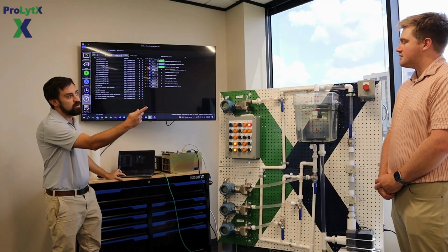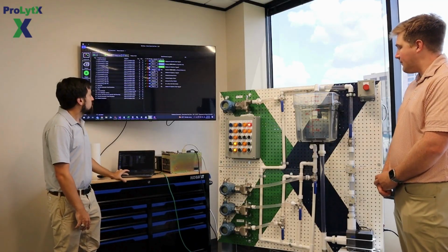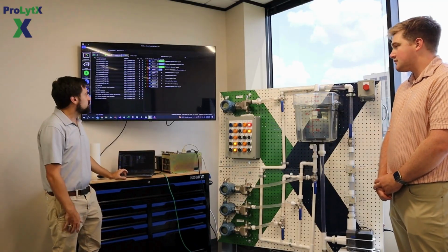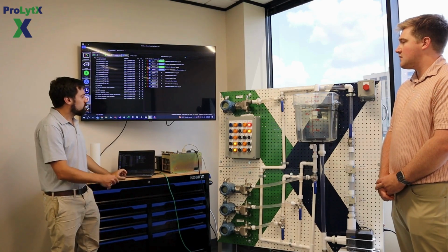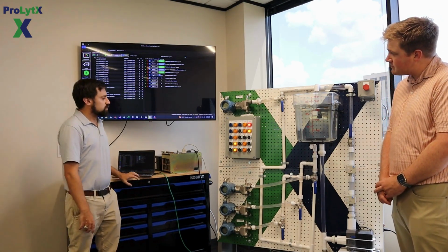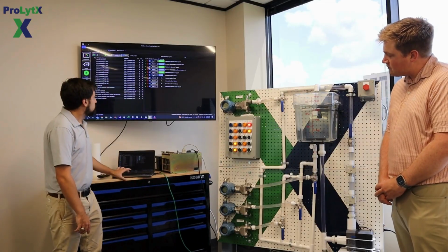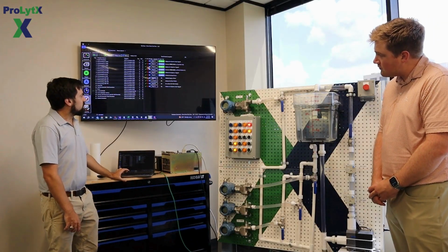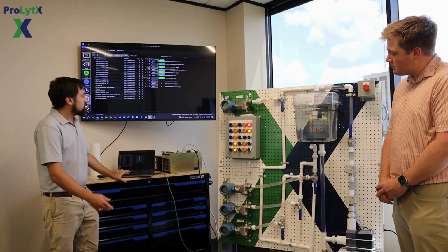The next step, we're going to put that ESD back to normal. Confirm the system's still tripped because the reset has not been hit yet. We're going to fix the valves real quick, so we should light them up. Right now we're closed on the valve side. Then we're going to validate that we're ready to reset through this light right here, and then we're going to hit the reset button. All right, I hear these opening.